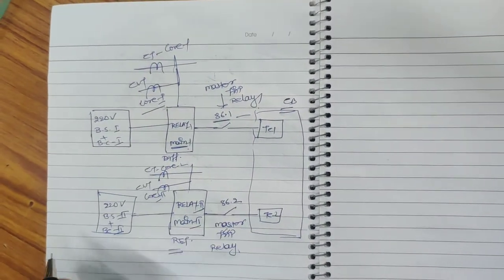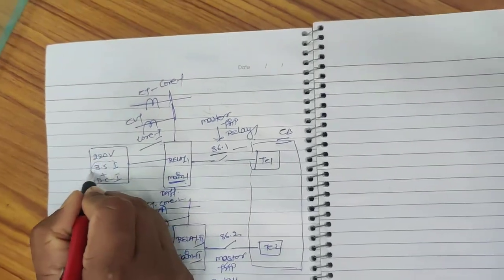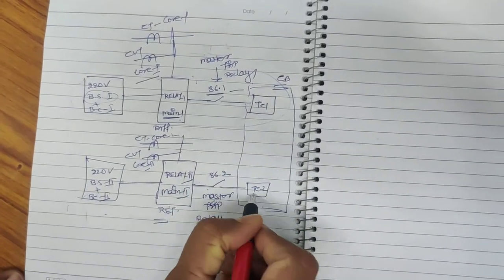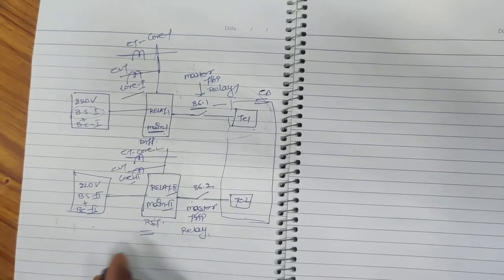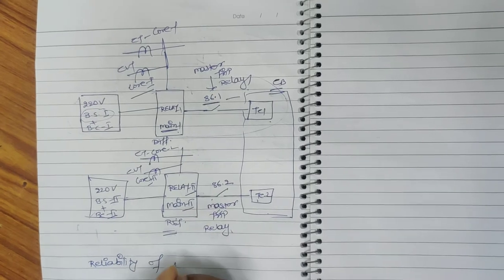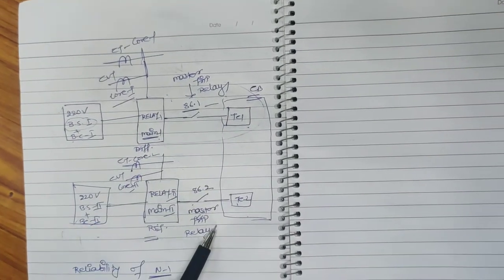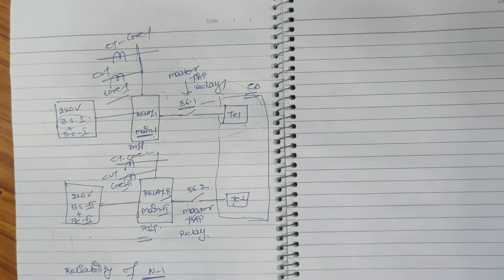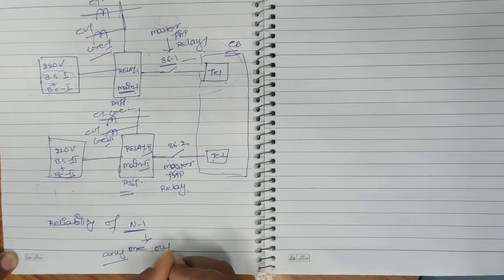If we count the elements in this protection scheme, we have approximately 14 elements in total — including battery systems, relays, master trip relays, trip coils, CT cores, and CVT cores. If there is a failure of any one element out of these 14, the fault will still be isolated. For example, if Battery System 1 fails, the fault will be cleared through Battery Set 2, Relay 2, 86.2, and Trip Coil 2. If Trip Coil 2 fails, the fault will be cleared through Trip Coil 1. If 86.1 fails, the other path will clear the fault. This is the N-1 reliability criterion — out of N elements, failure of any one element will not prevent fault clearance.